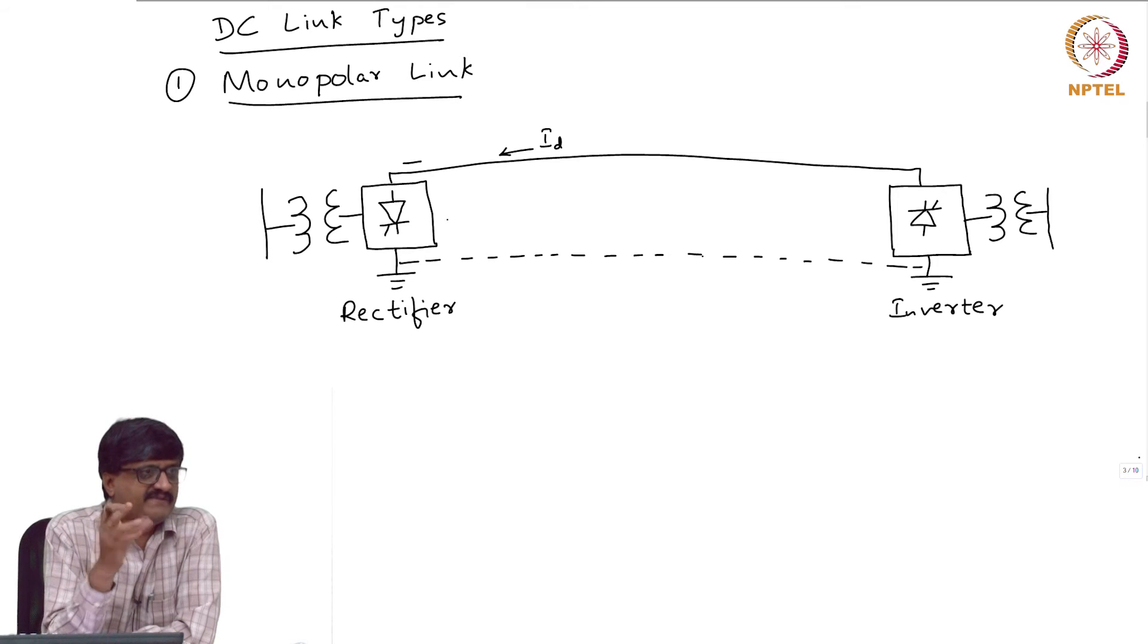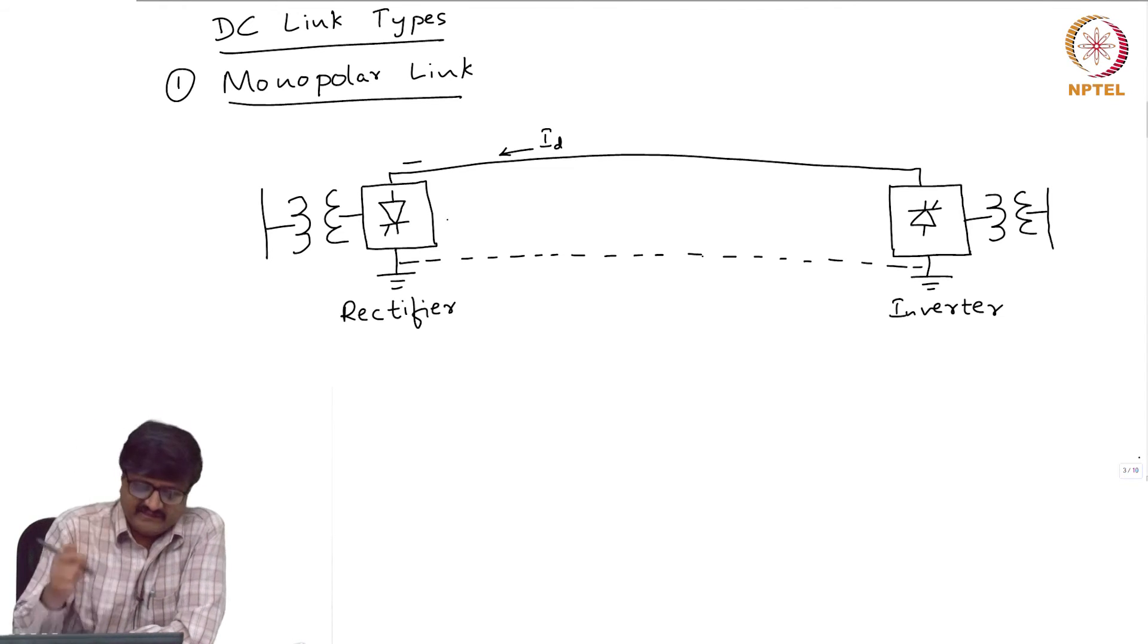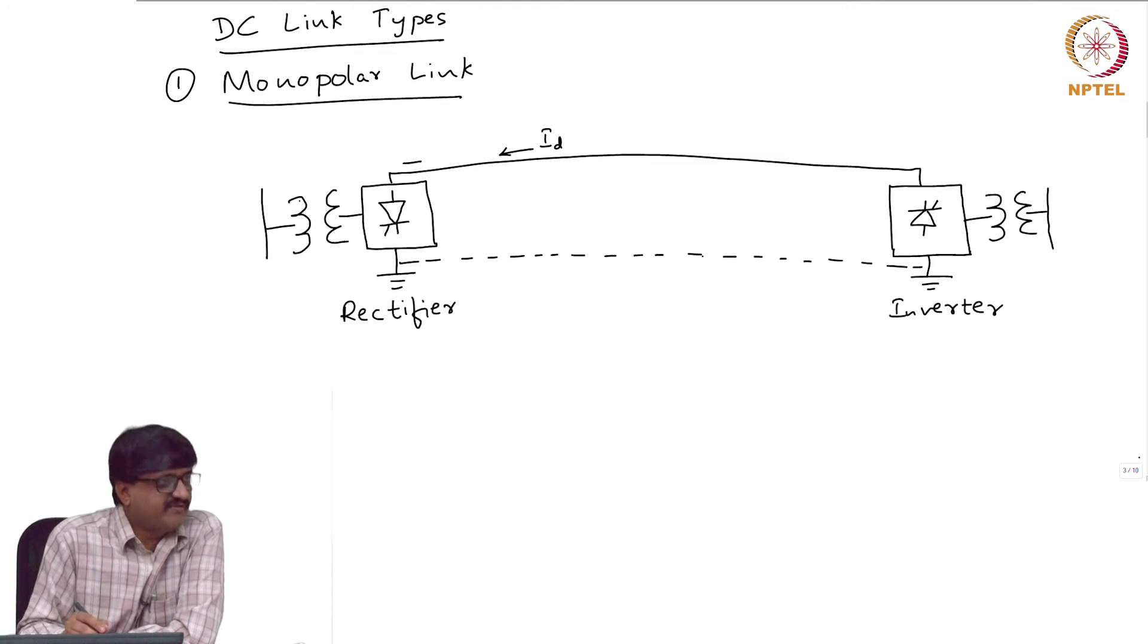If you look at a 12-pulse converter, there is a Y-Y and Y-delta transformer. There are two transformers and two 6-pulse converters. So that entire arrangement is shown as one transformer and one box with a thyristor. So this is the schematic representation of a 12-pulse converter.